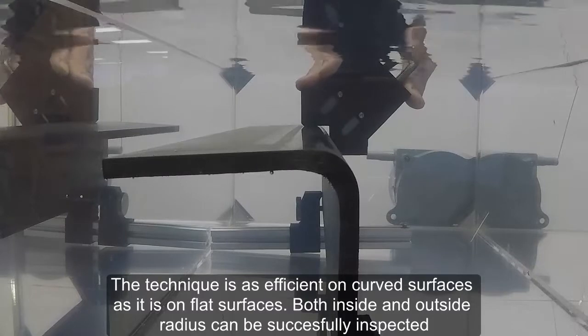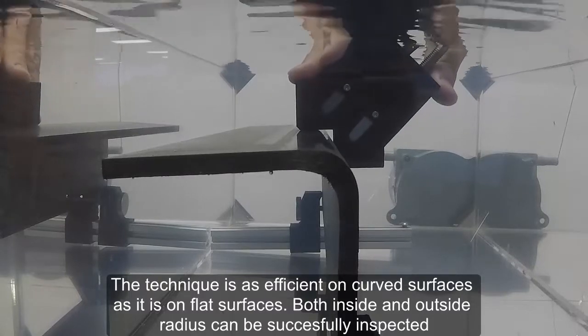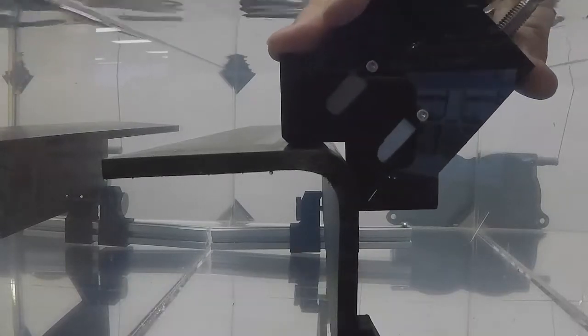The technique is as efficient on curved surfaces as it is on flat surfaces. Both inside and outside radiuses can be successfully inspected.